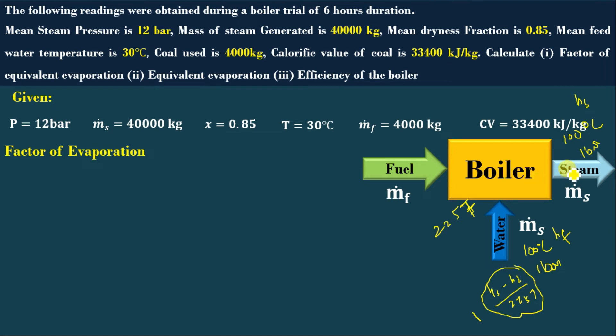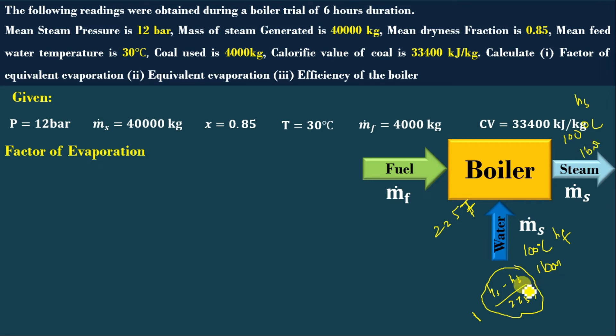For example, if the outlet steam condition is different from 100°C — say 250 or 300°C — then the factor of evaporation will be greater than 1. If the pressure is different also, it will be greater than 1. But for the same pressure, if it is wet steam, the factor may be less than 1. The factor of evaporation formula is: F = (Hs − Hf) / 2257.